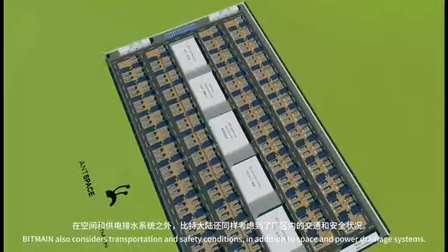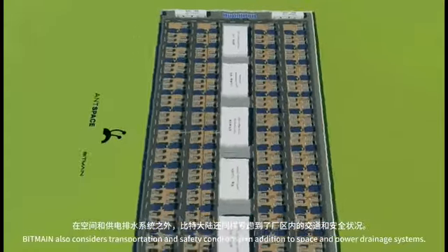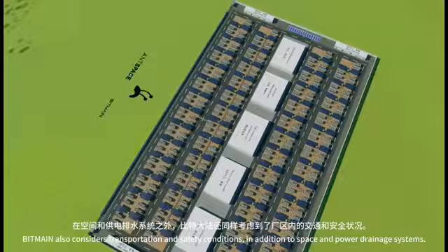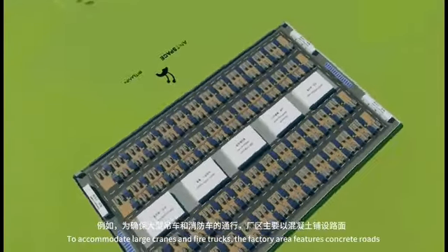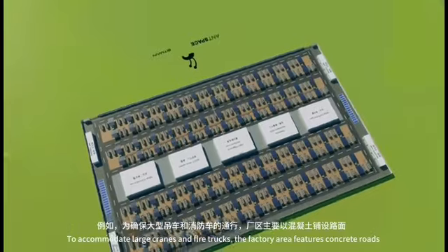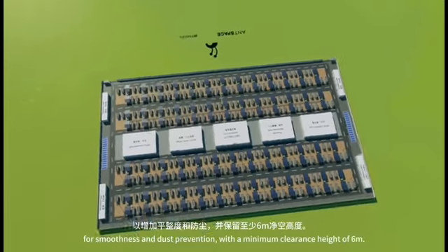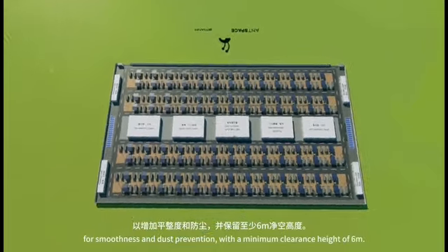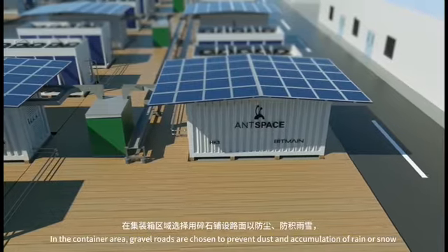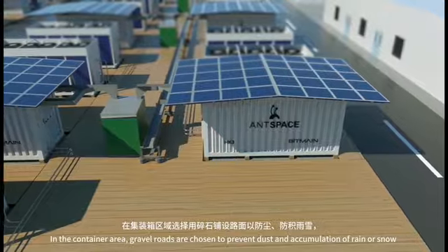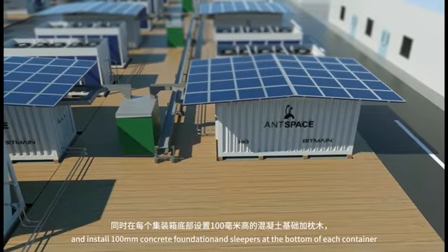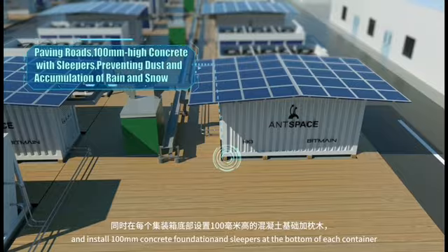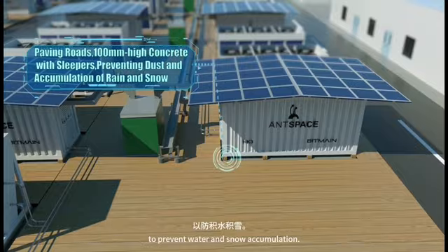Bitmain also considers transportation and safety conditions, in addition to space and power drainage systems. To accommodate large cranes and fire trucks, the factory area features concrete roads for smoothness and dust prevention, with a minimum clearance height of 6 m. In the container area, gravel roads are chosen to prevent dust and accumulation of rain or snow, and a 100 mm concrete foundation and sleepers are installed at the bottom of each container to prevent water and snow accumulation.